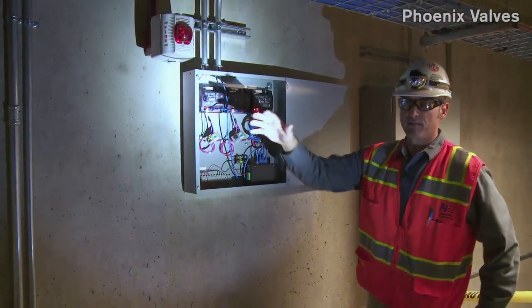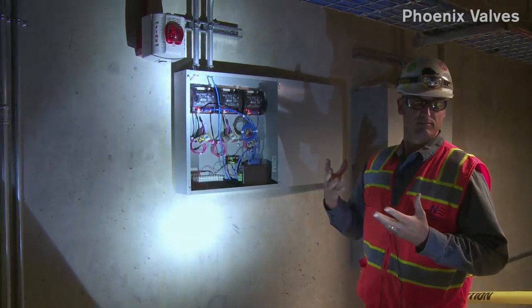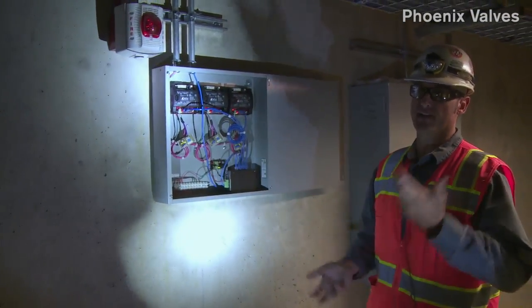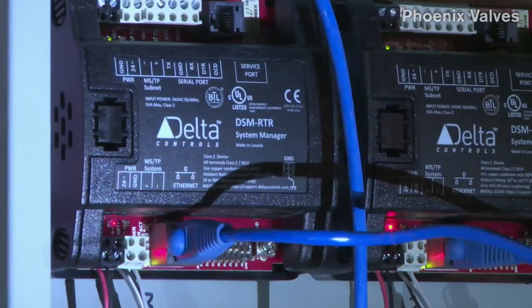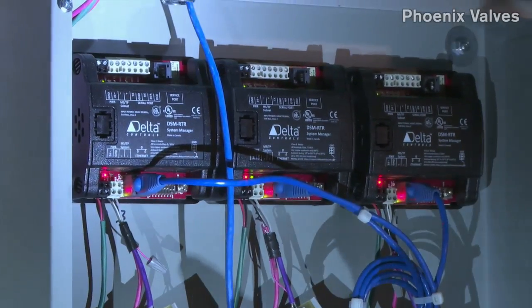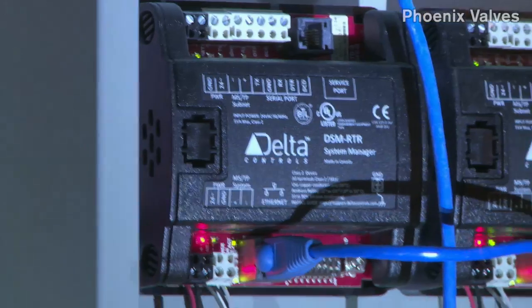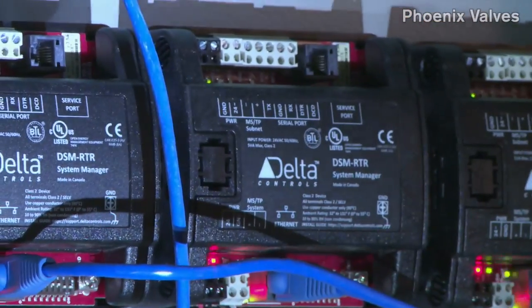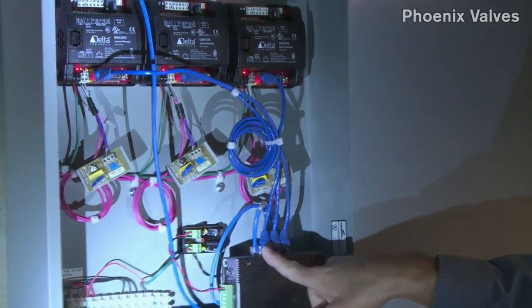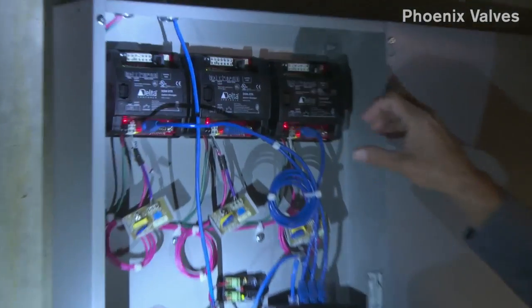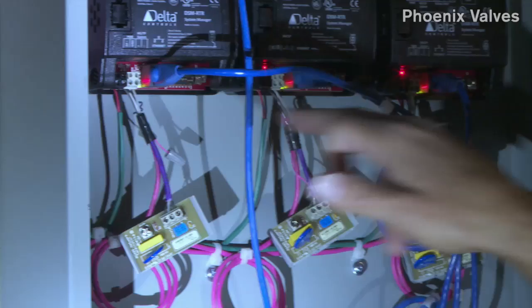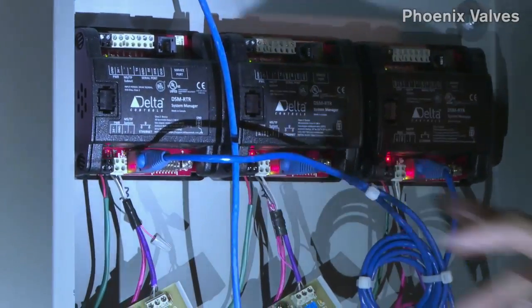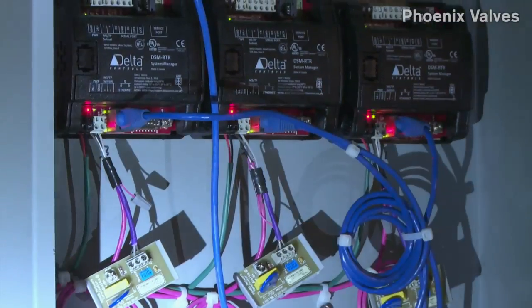All right, so as we were discussing earlier, you have some of your corridors where we have programs and code written in to maintain polarities and everything. That's where it's all coming back to these routers. There's 3 routers, 3 different zones in this vivarium for the actual count of all your BACnet devices. We had to separate it down to 3 controllers. These all go through Ethernet, and Johnson Controls is connected into here as well. These are the main brains. They're all divided down. We have a sheet that lists router 3, 2, and 1. We have sheets that say what devices are all on each router, so you'll know which corridors.